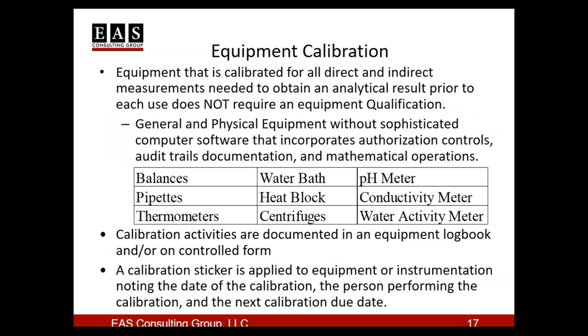Then we have the calibration of equipment. We talked about that earlier. This is often done during the PQ portion of the IQOQ-PQ. But if not, there are some equipment that don't necessarily require a qualification. These are general and physical types of equipment that are calibrated each time they're used.